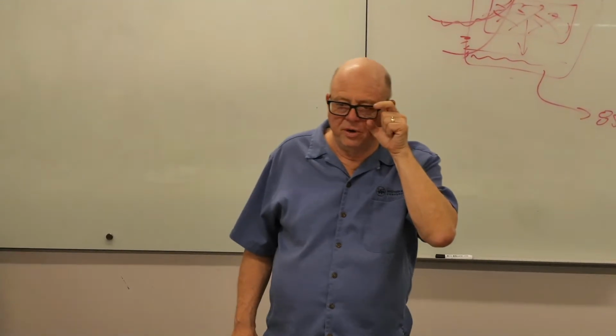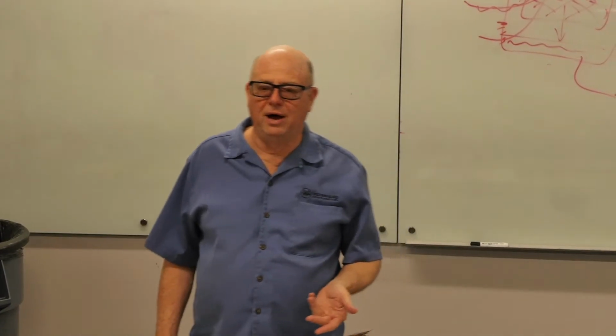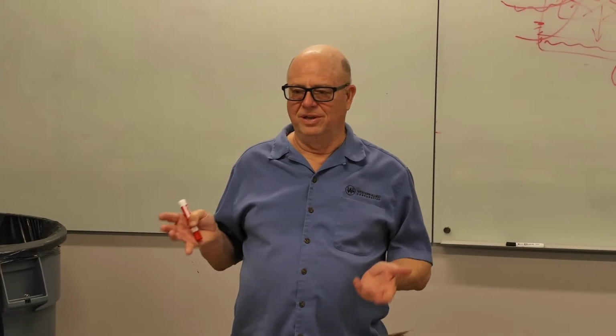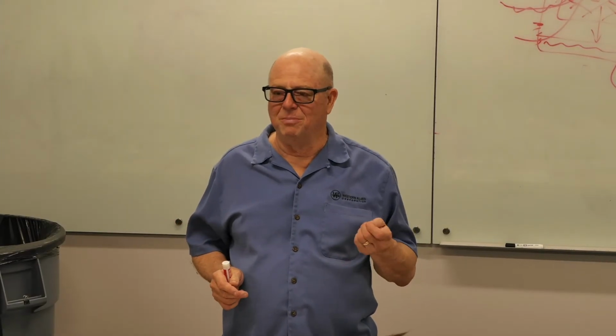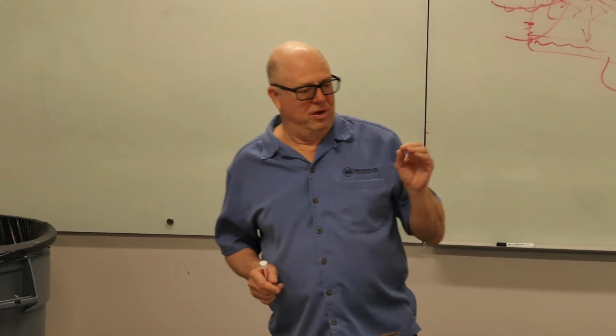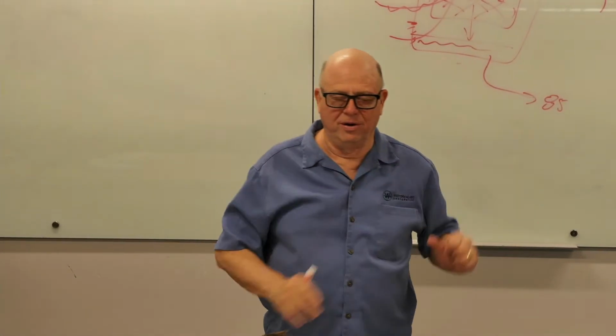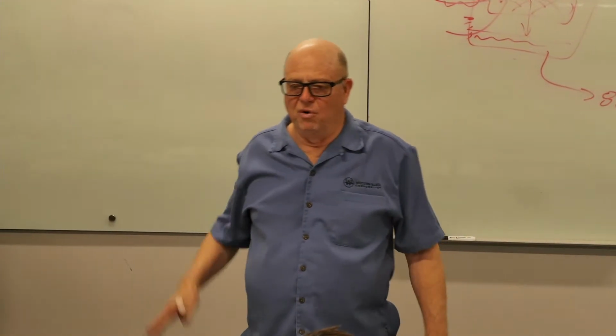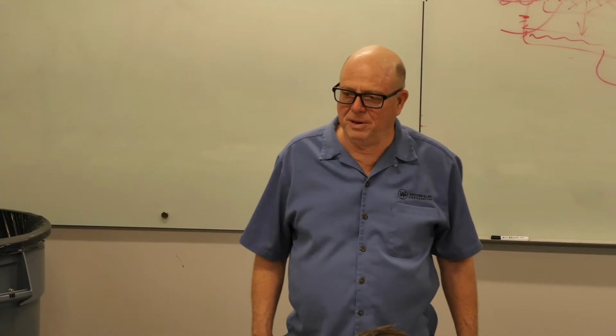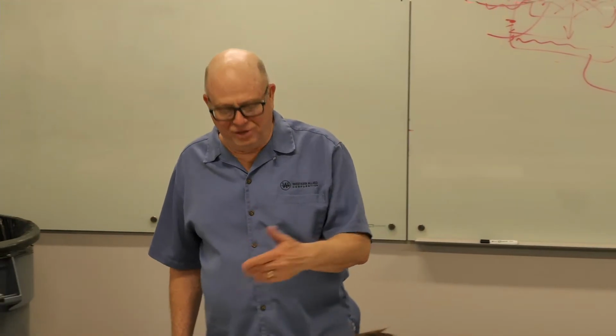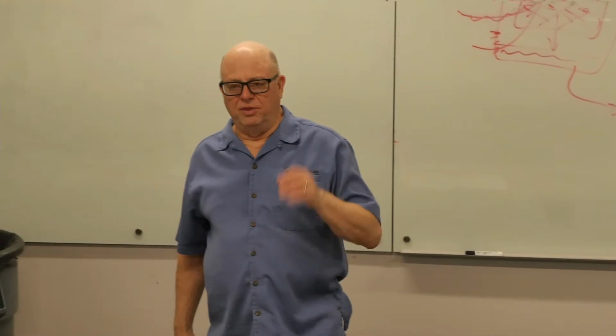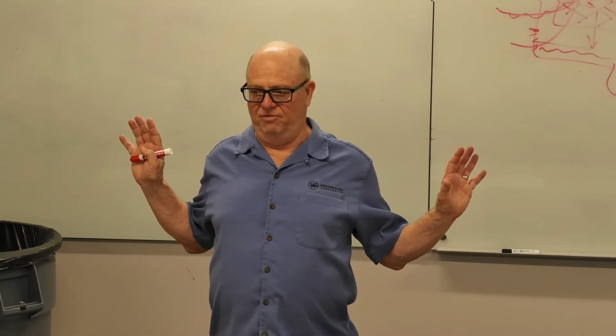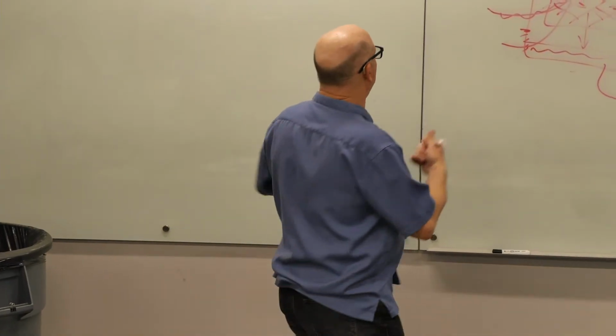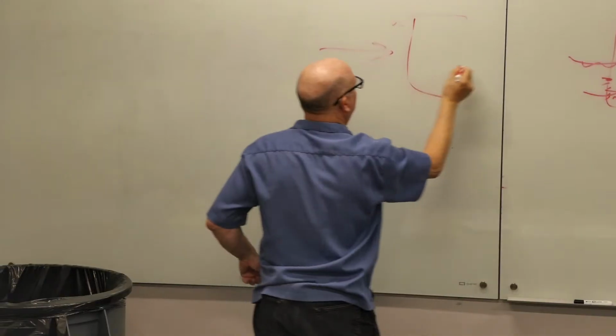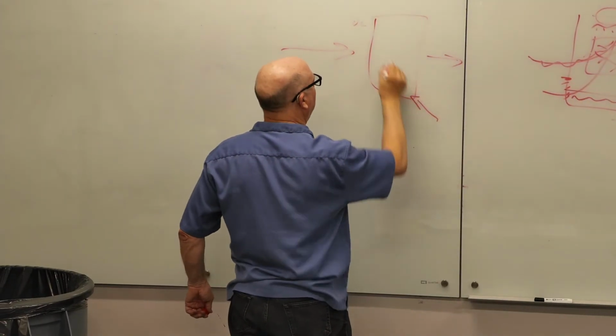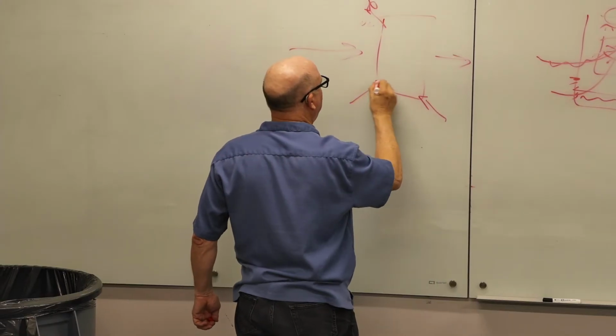I was looking through material to try to use for this class, and I pulled out some of my old Carrier stuff from the late 70s and early 80s. I found a memo from 1979 where the air handler group in marketing at Carrier was castigating all the salespeople for not making sure that the customer knew that they had to pipe counterflow.